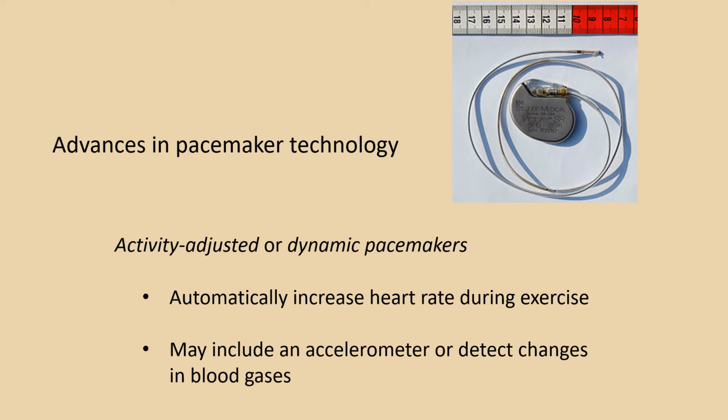Pacemakers have gotten more sophisticated recently, in the last decade or so. We now have dynamic pacemakers, also known as activity adjusted pacemakers. They have additional devices in them that can determine when you engage in physical activity. They might have an accelerometer that can detect changes in the movement of your body, and some of them have chemical sensors that detect changes in your blood gases, which would occur with the onset of physical activity.